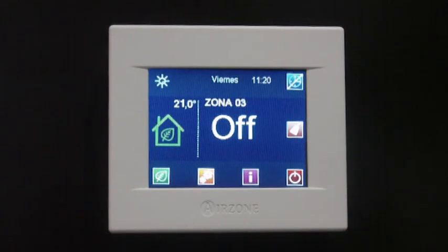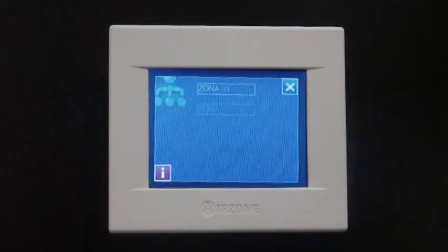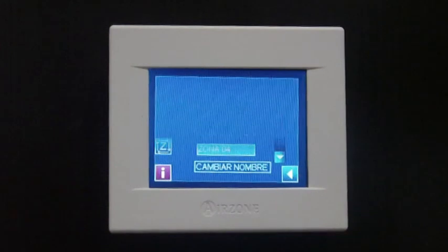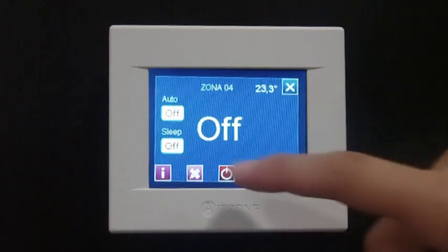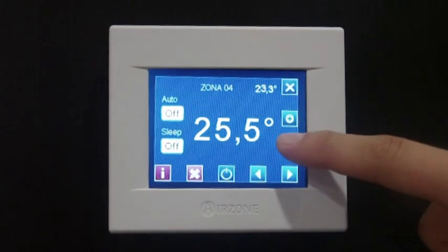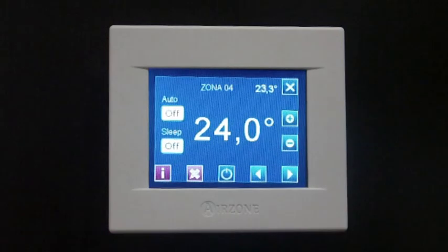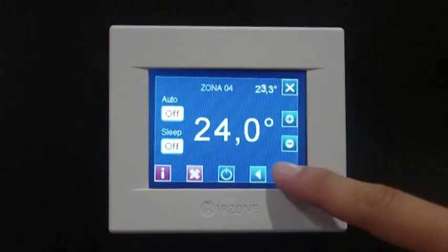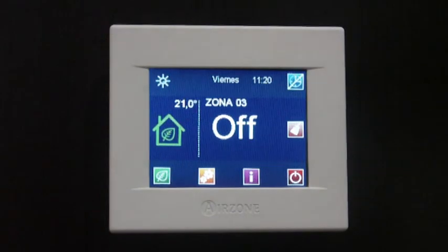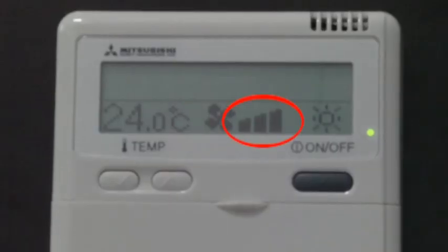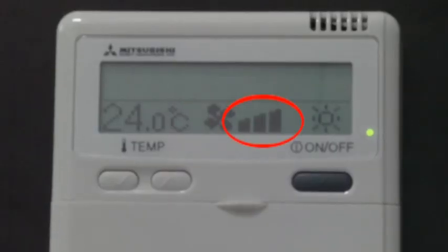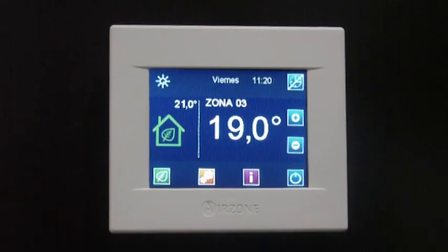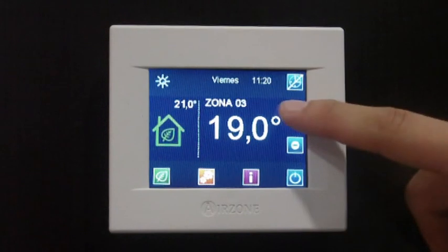Airzone communication gateway also sets the indoor unit fan speed, so that the performance of the system is adjusted according to the dynamic behavior of the installation. When there is one zone in demand, the system will set the indoor unit fan speed to the minimum available. If the number of zones on demand increases, the indoor unit fan speed will increase accordingly.